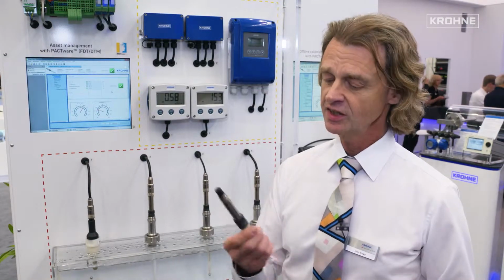The benefit of this system, since other companies also offer a kind of electronics with a sensor, is that here it's absolutely free communication, because this sensor talks 4 to 20 milliamp. Everybody knows it, everybody can use it, it's very simple. This electronics also talks HART 7, which is an open standard.